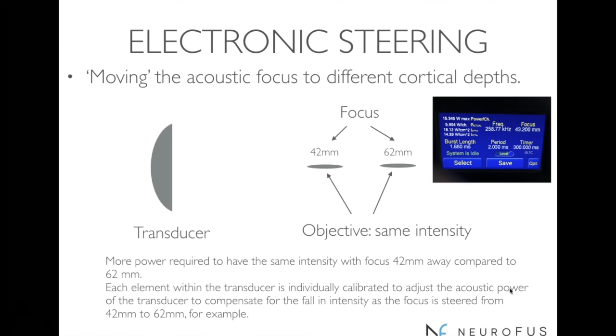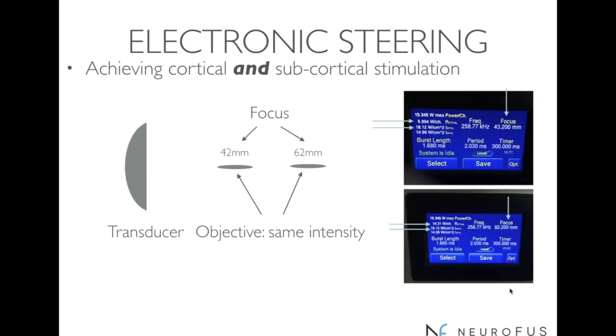It can achieve the same ISPPA at two different distances by changing the power of each element within the transducer. And each transducer is individually calibrated in a water tank.